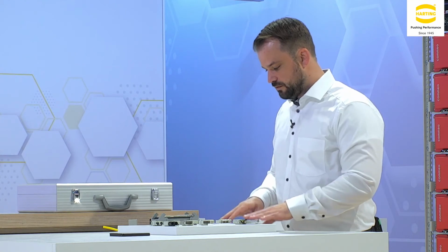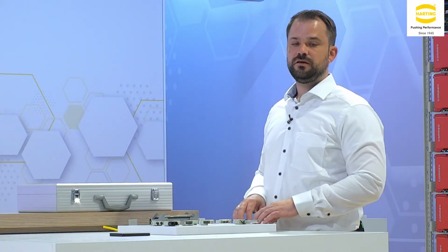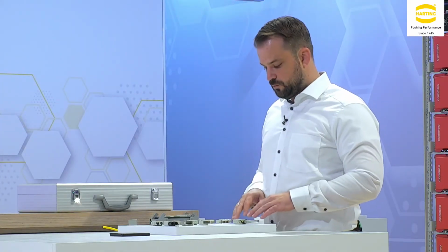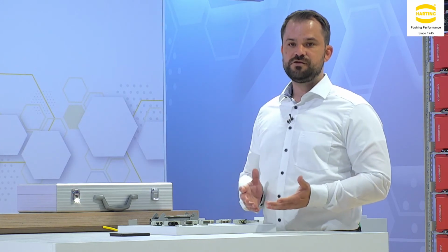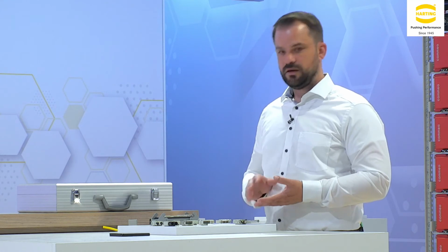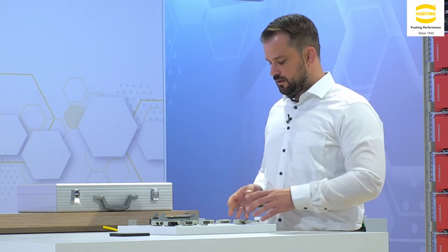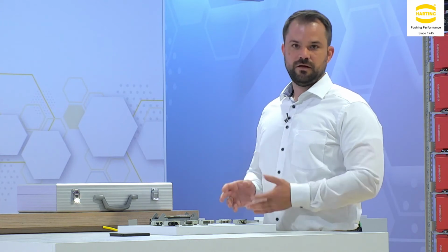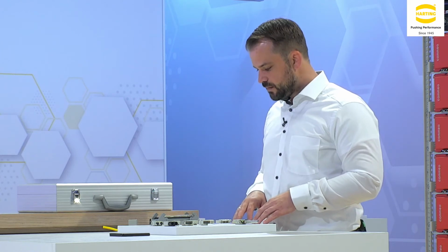And since we are at that shielding principle, the last module that I want to introduce to you with this shielding principle is our shielded power module. The shielded power module was created to be implemented between a frequency converter and a drive. So we have created this module especially for this application, and also the number of pins, meaning we have 4 power pins and 2 signal pins, is very specific for this usage.